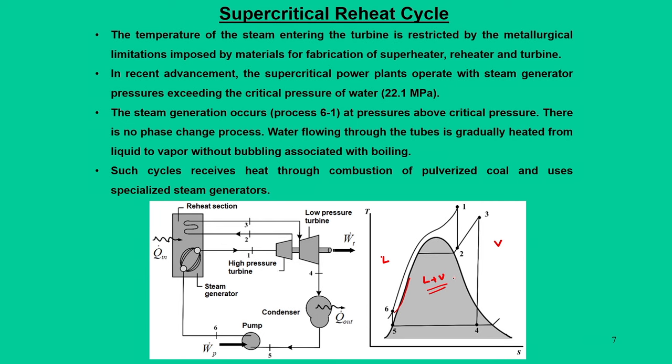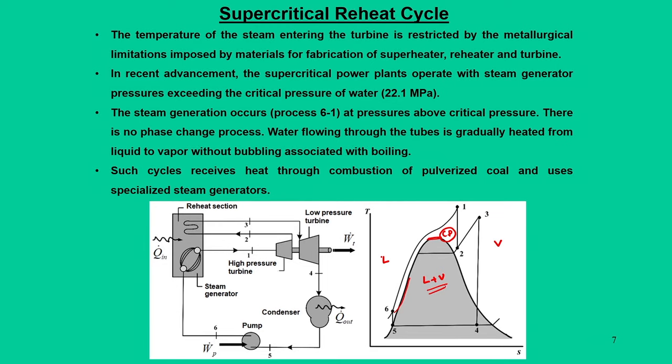What the supercritical system does is increase the pressure such that we cross the critical point, so that liquid directly goes to steam without passing through the liquid-vapor region. The steam generator is equipped in such a way that we create pressures where liquid water goes directly to steam, which means we must operate at pressures above the critical pressure.